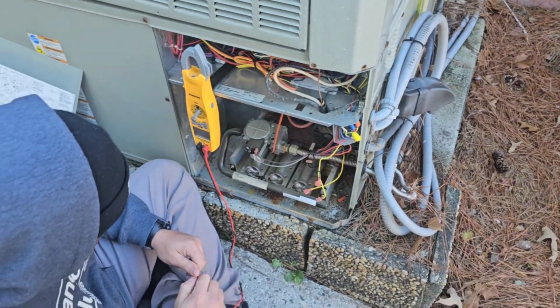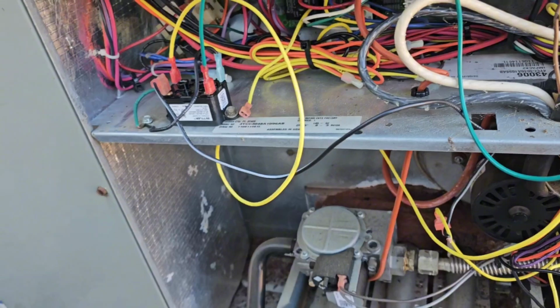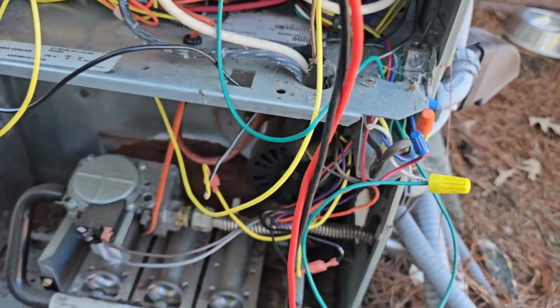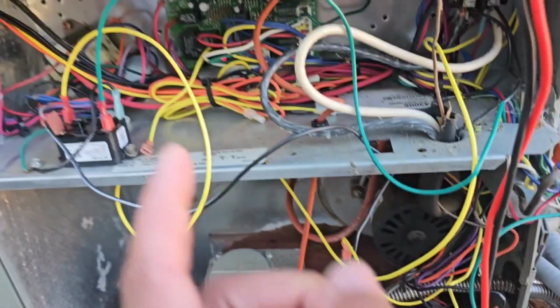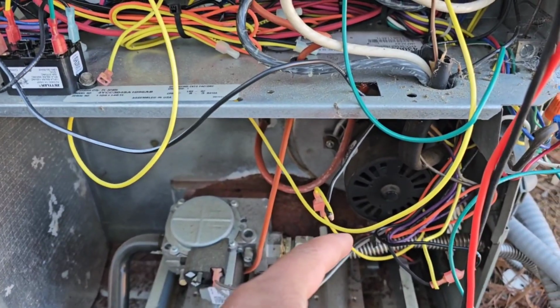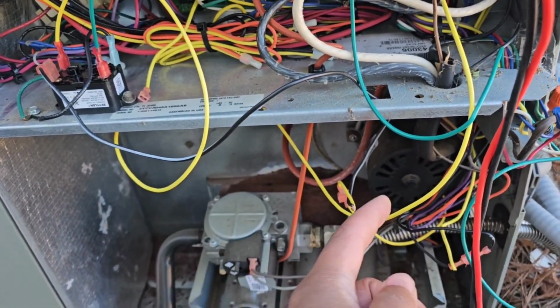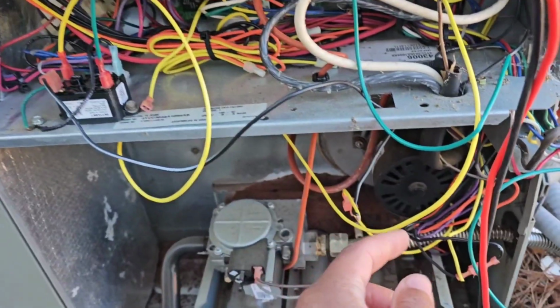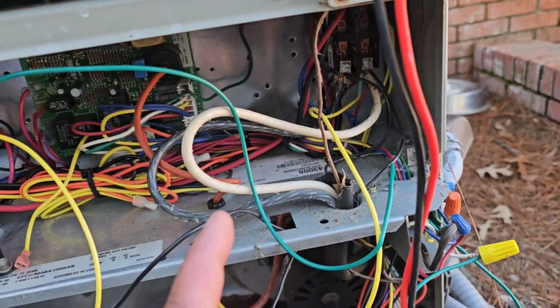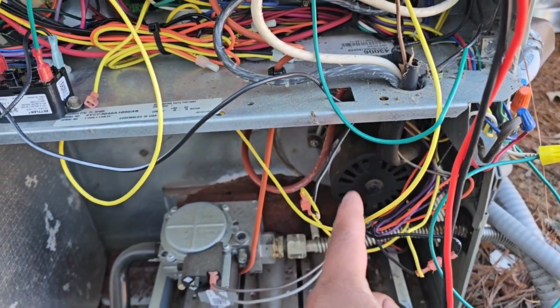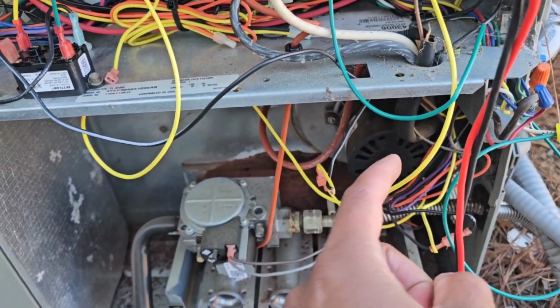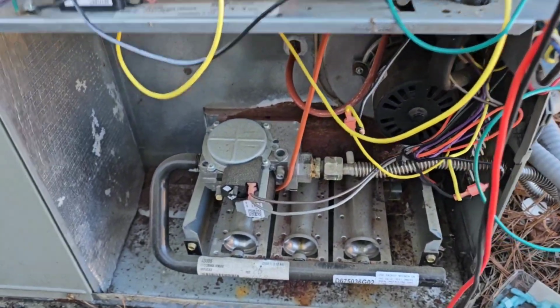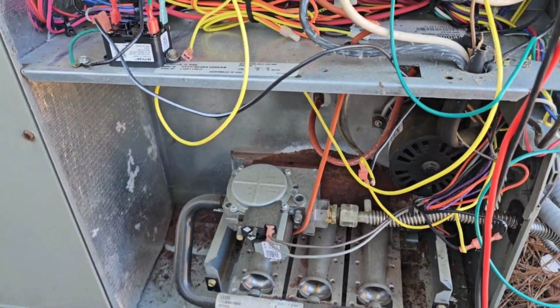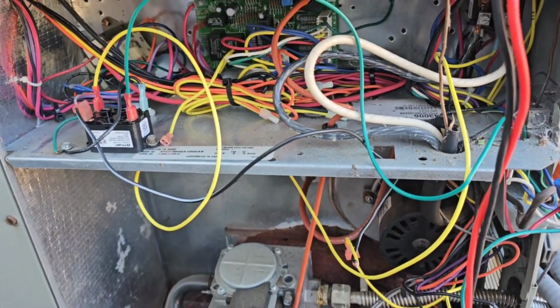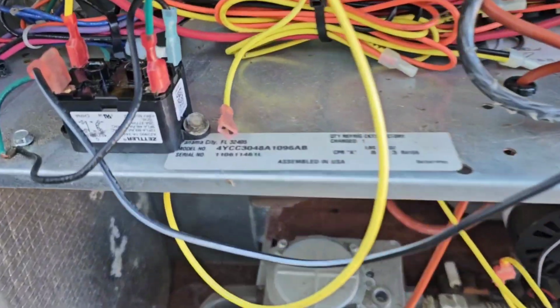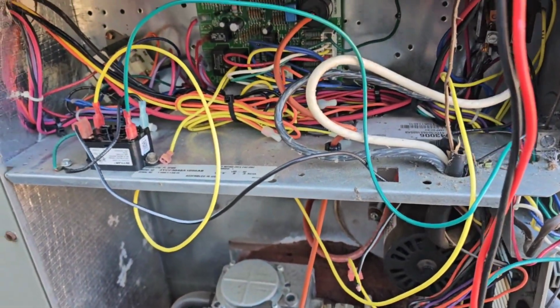Let's dive into this a little bit more. After a good amount of trial and error, got a 4-pin relay in here to click on when there's a call for heat. We did that since we know the board's not sending the full 240 to the motor. I bypassed the board, knowing we have 240 now, because that's tied straight into the bottom end of that contactor over there, the motor's still bad. So we verified that. If it would have at least made flame, I would have let it go just to get these people heat, because it's freaking freezing out here right now. But I doubt this unit is still under warranty, so there's gonna be a pricey fix here.